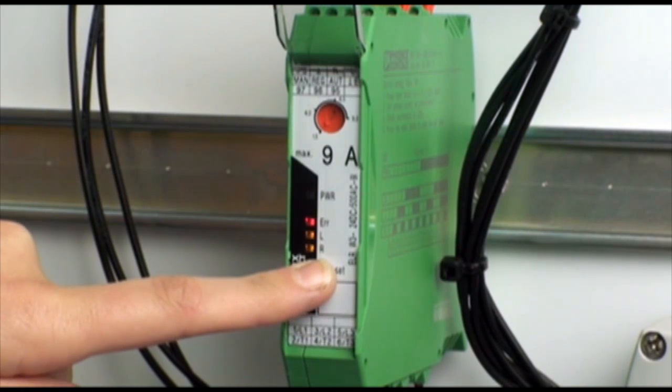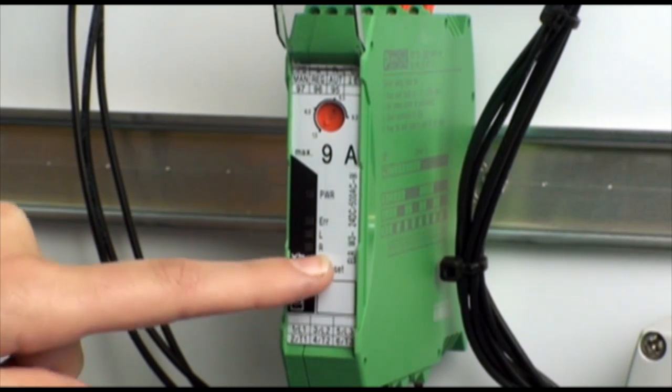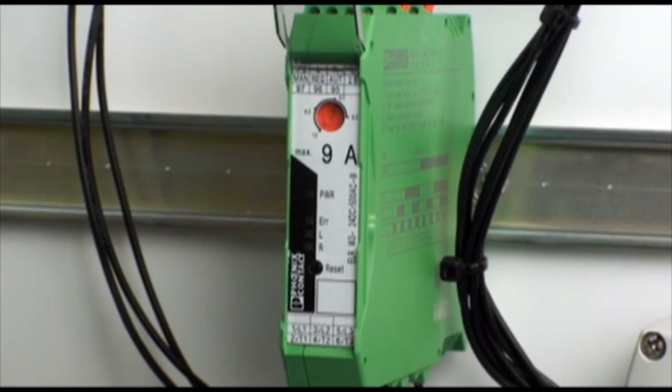If you don't push the reset button in first, you can turn the adjustment dial, but you won't actually change the overload trip setting.